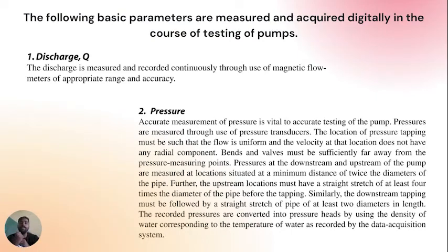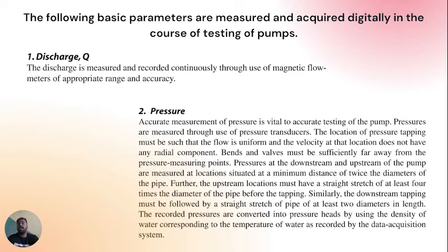Basic parameters measured and acquired digitally during pump testing: discharge Q is measured continuously through magnetic flow meters of appropriate range and accuracy. Pressure measurement is vital to accurate testing — pressures are measured through pressure transducers. The location of pressure tapping must ensure uniform flow with no radial velocity component; bends and valves must be sufficiently far away from pressure measuring points.